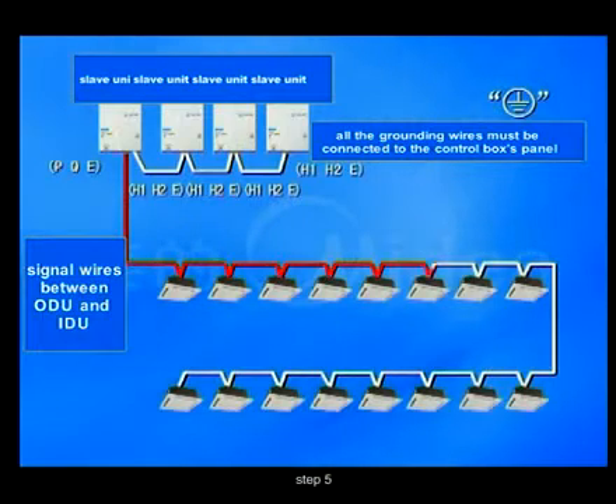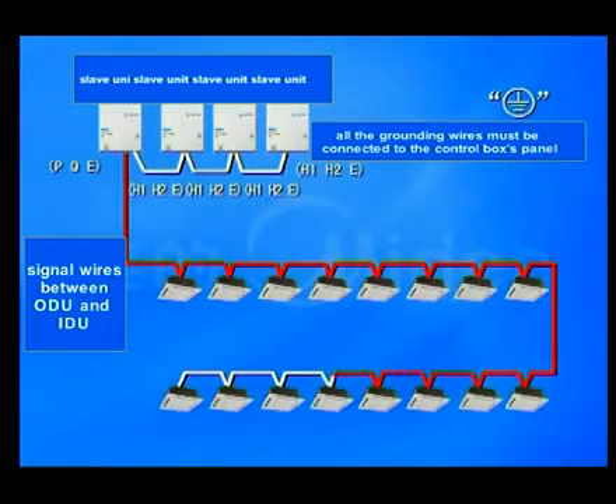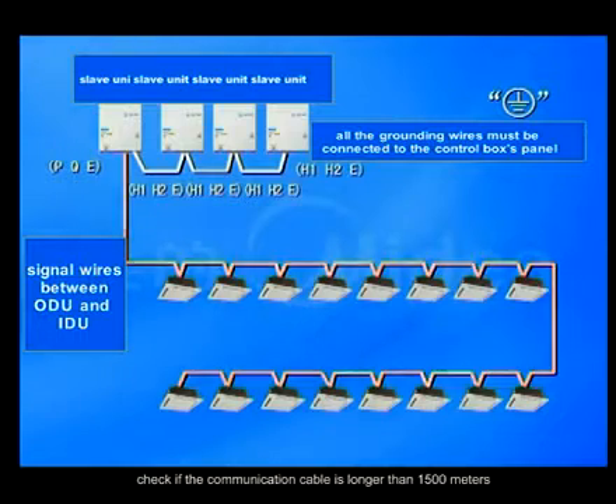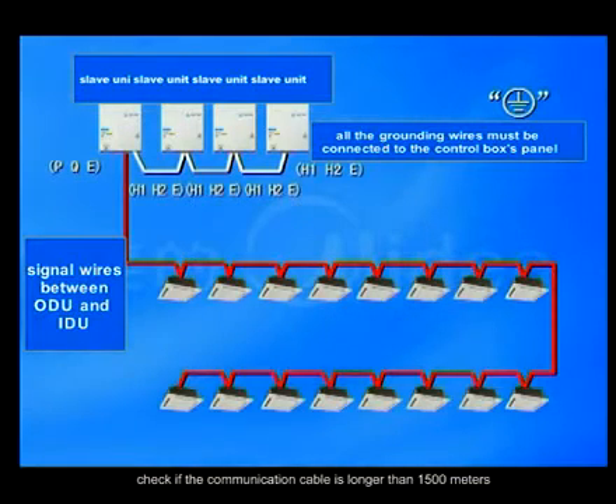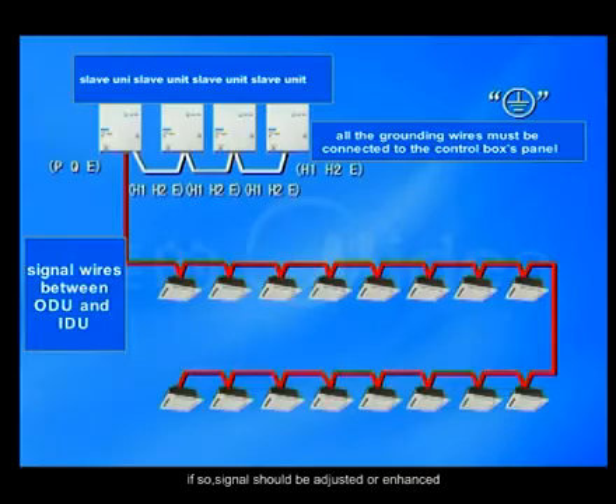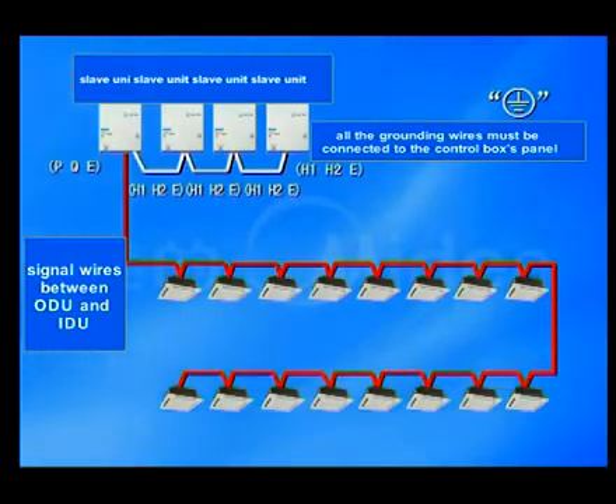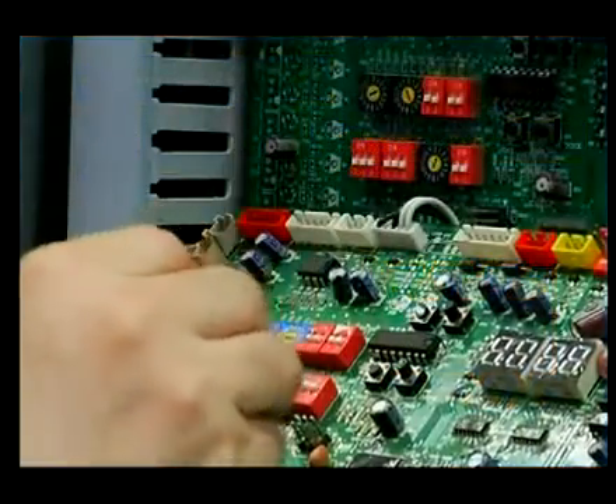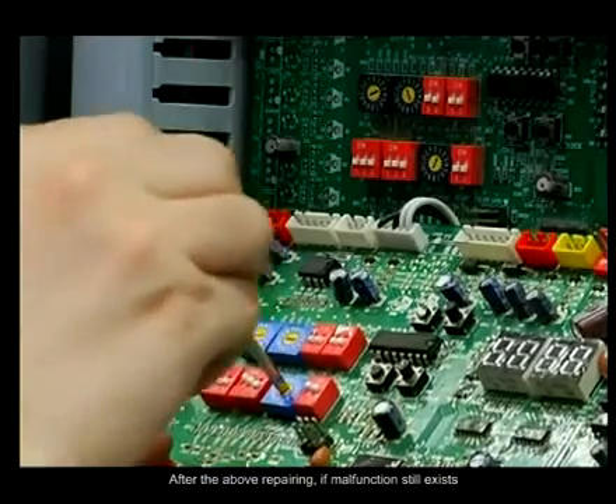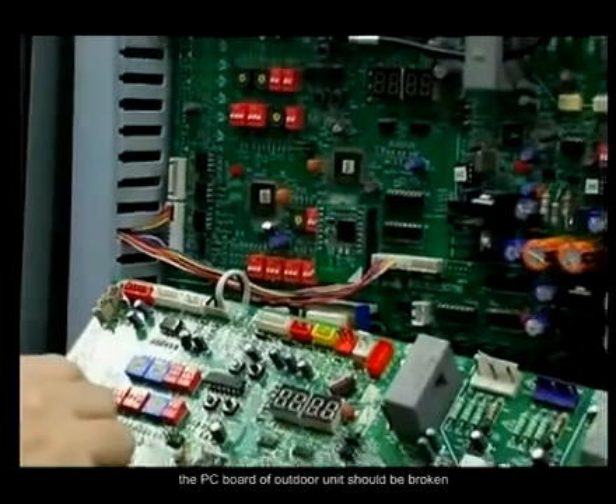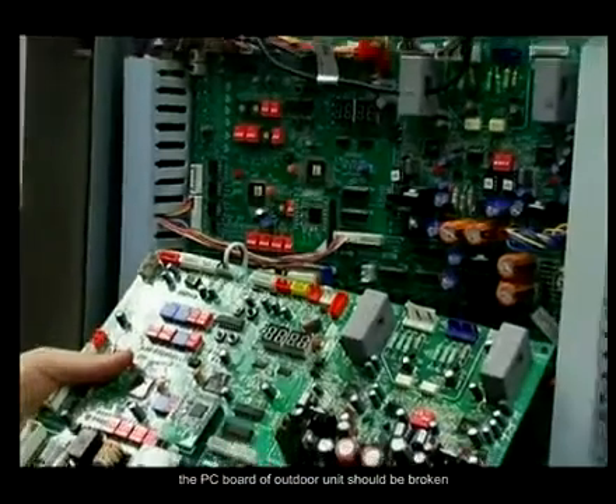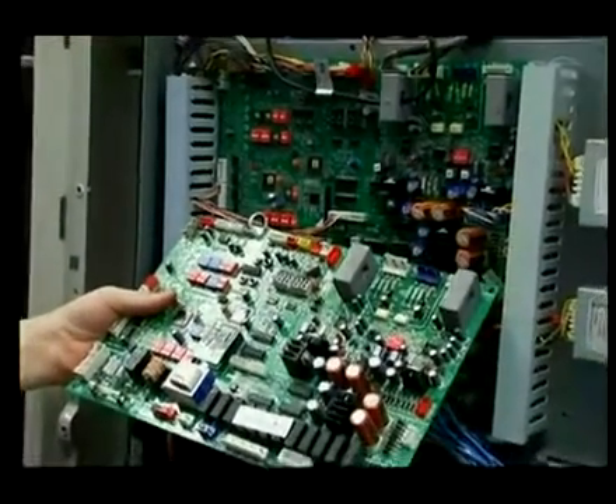Step 5. Check if the communication cable is longer than 1,500 meters. If so, the signal should be adjusted or enhanced. After the above repairing, if the malfunction still exists, the PC board of the outdoor unit may be broken. You have to replace it with a new one.